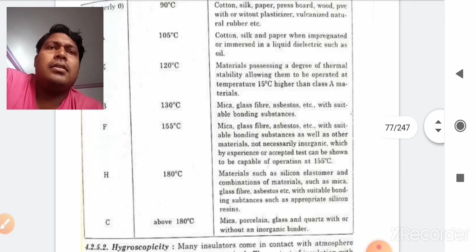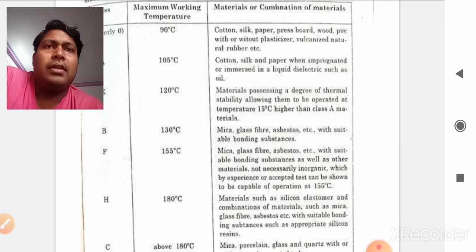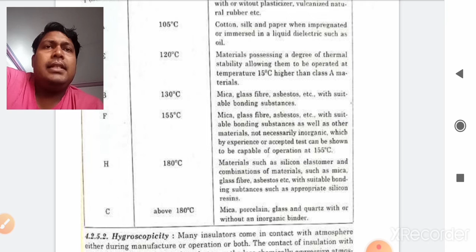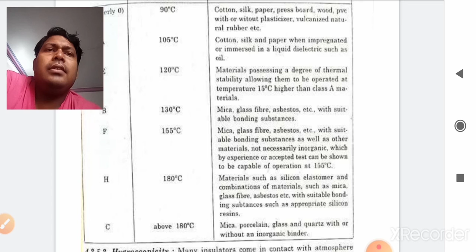Obviously from the table it is clear that you will select H or C, because the working temperature is 170. So I cannot go for F, because F will provide me only 155. So I have to go beyond. So I will select simply H or C, considering the temperature variation or fluctuation is within limits of 1 or 2%. So here we will decide after having the knowledge of the classes of your insulation.